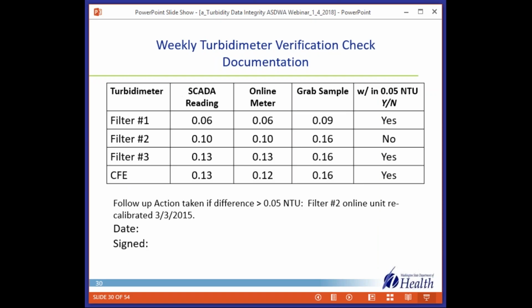Looking at documentation for that verification check is also very important. This is an actual form used by a treatment plant. They have 3 filters. If you look here, they go on a weekly basis. They read their SCADA reading and compare it to their online meter reading and record those values. And then they have a grab sample, and then they mark yes or no, is it within 0.05 or not. So here on filter 2, the SCADA and online match, but the grab sample is significantly different. It's out of spec. So down below, they mark what do you do if you get a difference greater than 0.05? And in this case, filter 2 was recalibrated on the date and passed.